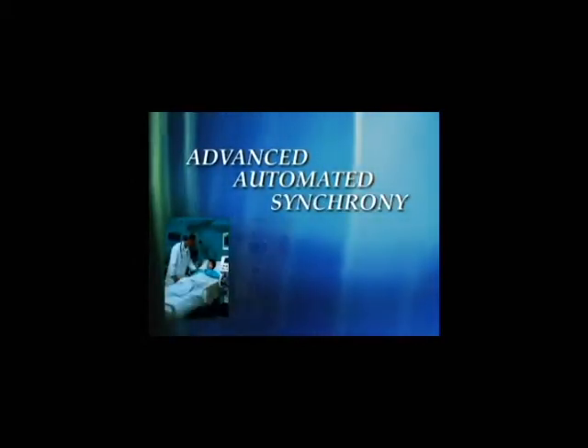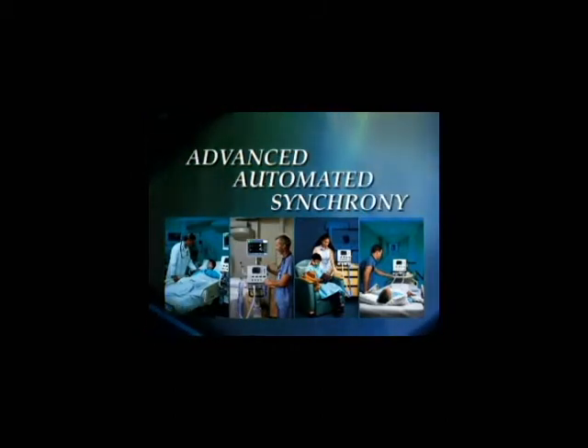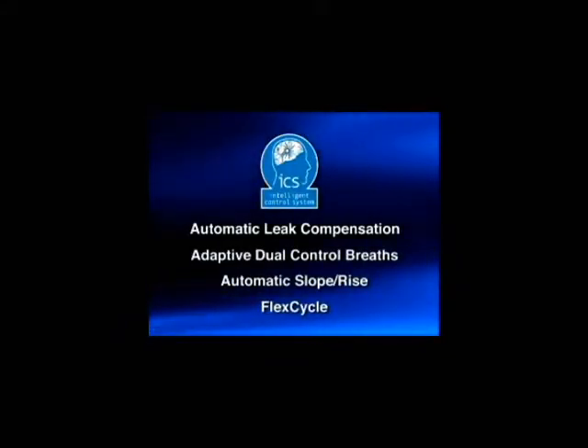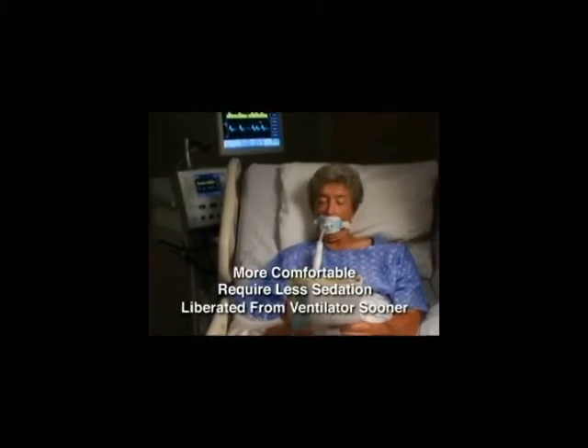Advanced automated synchrony: improving pressure support breath delivery with Newport Medical's automatic slope rise and flex cycle. One of the worst mechanisms responsible for breathing discomfort during artificial ventilation is the lack of synchronization between the neuro inspiratory time of the patient and the mechanical action of the ventilator. Newport Medical has developed the Intelligent Control System — a group of automated functions designed to improve total breath synchrony, so patients can be more comfortable, require less sedation, and are liberated from the ventilator sooner.